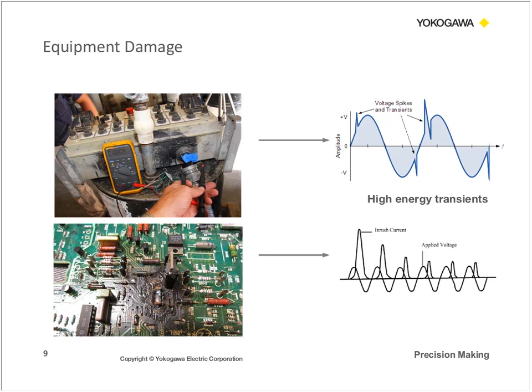And really, equipment damage can also occur when you have high energy transients. These transients come from lightning strikes, power outages, short circuits that we've made, or even power line malfunctions from the power company. Although uncommon, these transients can occur, and they do cause equipment failures that end up costing not only time, but a considerable amount of money to fix. And for sensitive electronics, it doesn't take much transient energy to really damage the internal circuitry.